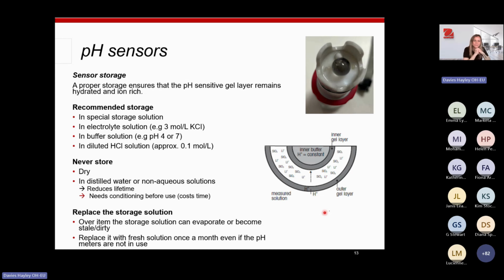electrode. If you've allowed your electrodes to get dry, so you found one on the desk the next day and it's gone dry, we can recondition them. I will go over some tips on how you can recondition the pH electrodes before you write them off. So never store them dry, never store them in distilled water. It needs to be in this nice ion-rich solution.